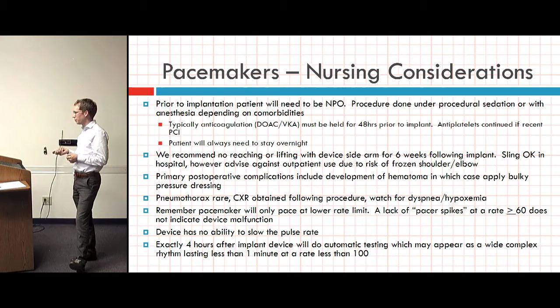And again, we can't slow the heart rate down. So if the rate's above 60, the pacemaker's doing its job. With these devices, and Mike will talk about this as well, after the implant there's this automatic testing, which is a run of pacing, usually at a rate around 90 or 100. That's the device checking to see what voltage it requires for capture. You'll see this and it'll look like a slow ventricular tachycardia, but it's just automatic testing on the device. So if it's wide but not fast, it's likely coming from the device. It doesn't always show pacer spikes in that case.